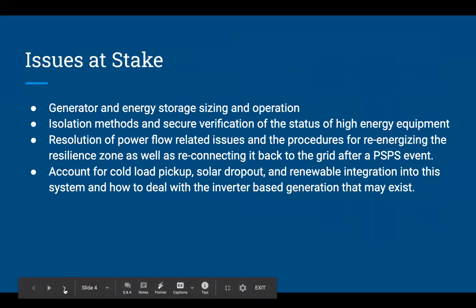Next up, we have the issues at stake, which includes the generator and energy sizing and how they are going to operate, figuring out the different isolation methods and how to verify the status of high energy equipment, as well as resolving power flow related issues and the procedures for re-energizing the resilience zones, as well as reconnecting it back to the grid after a PSPS event. These issues will also include accounting for cold load pickup, solar dropout, and renewable integration into the system.